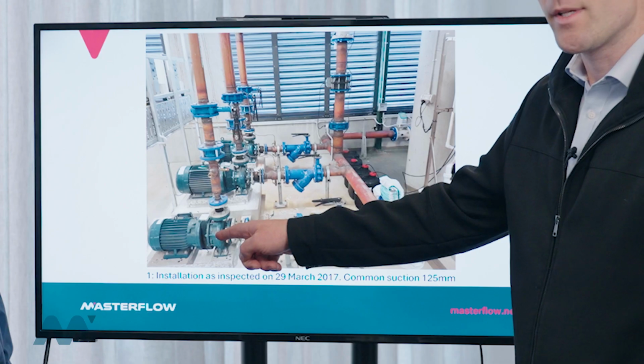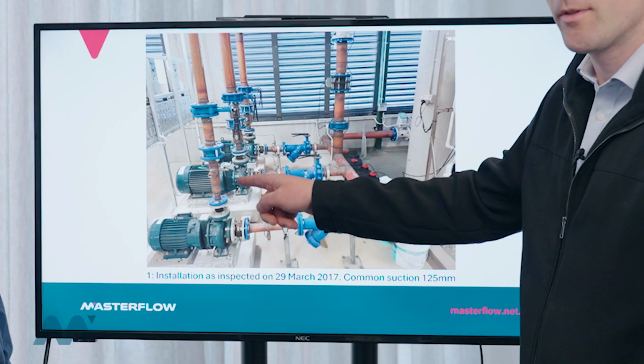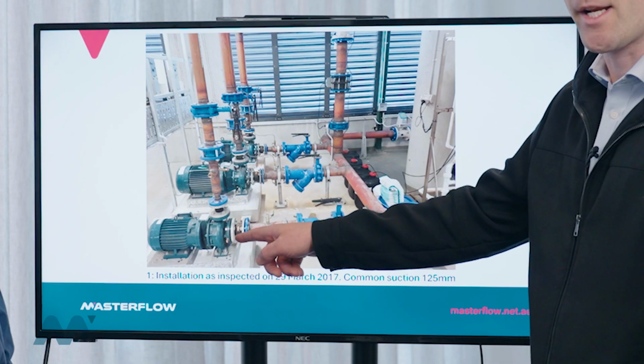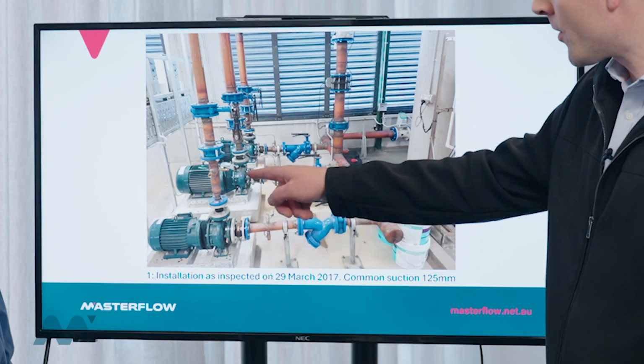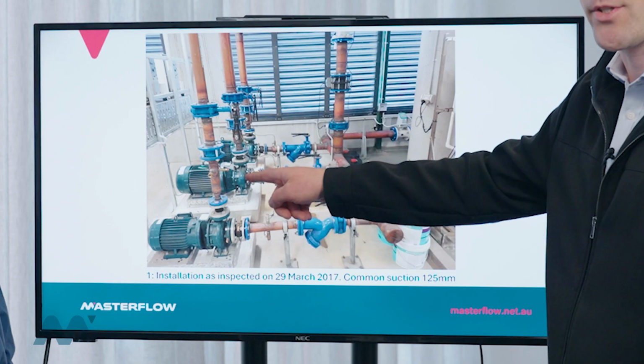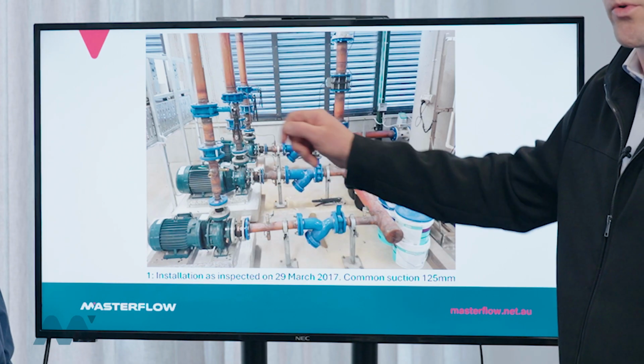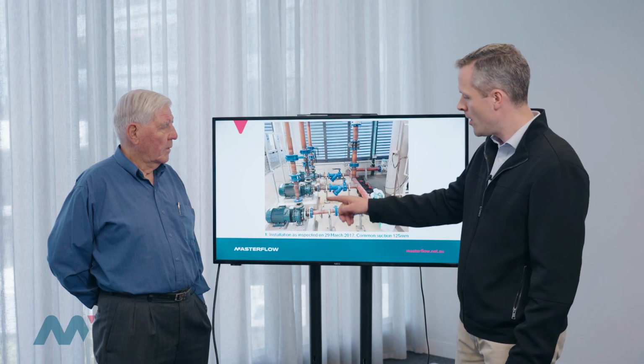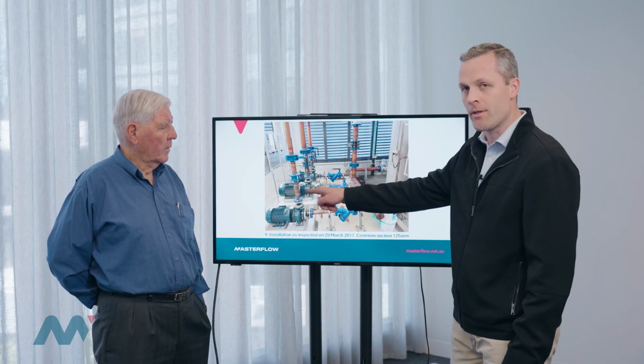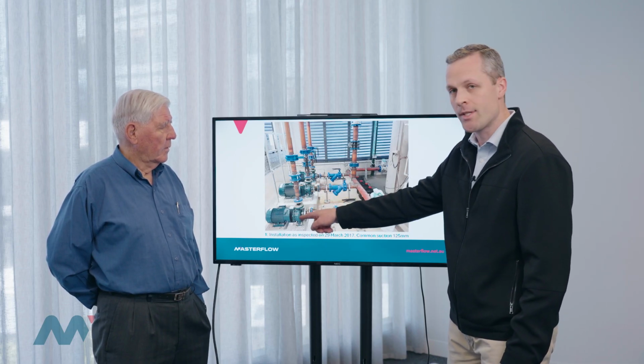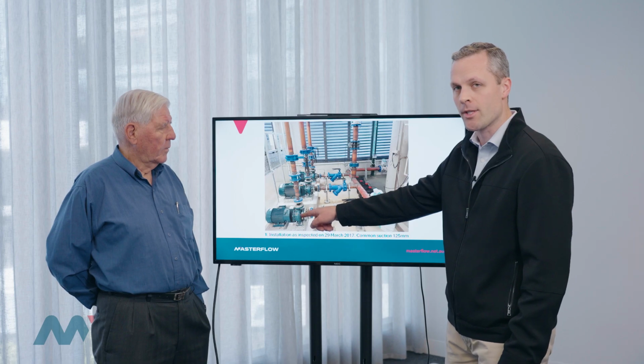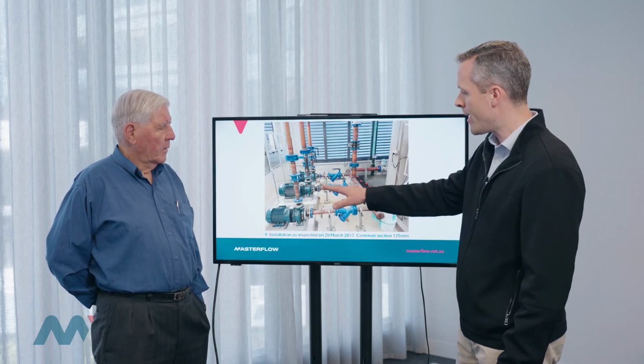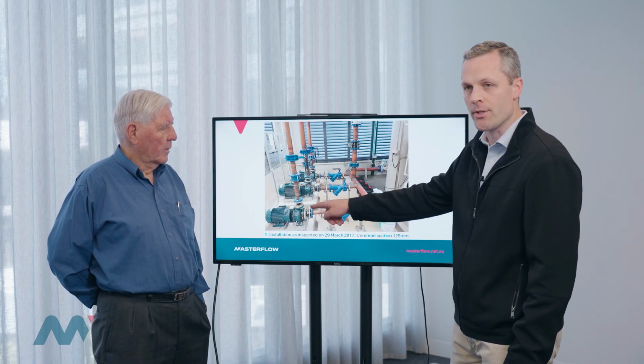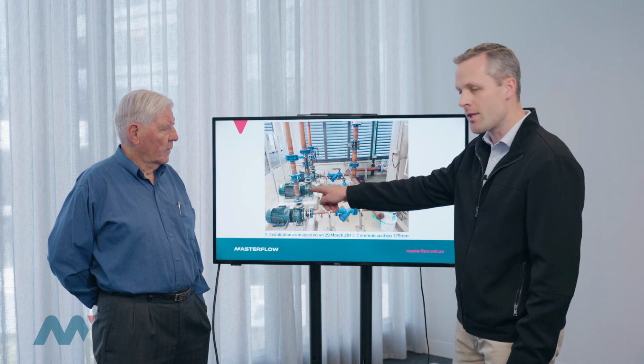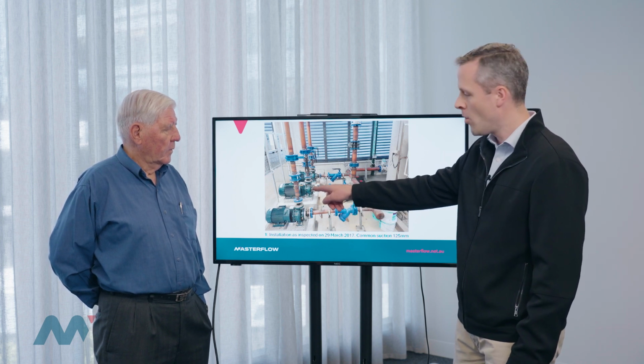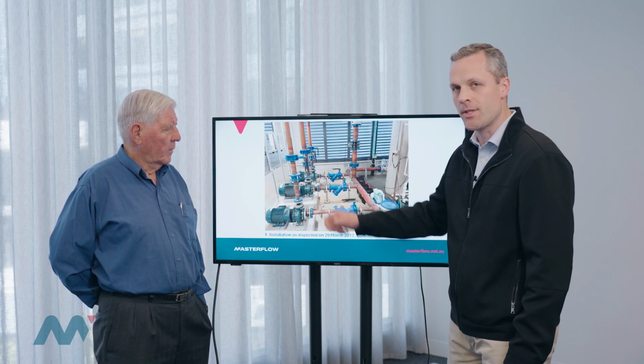This particular pump is a smaller size than these two because this pump is feeding the tenancy condenser water system, whilst these 2 pumps here, which are larger in size, are feeding the chilled water system. At any given time, we could have one of the pumps feeding the chiller system and the tenancy condenser water pump operating at the same time. What we don't have is all 3 operational at the same time. So it's either one of these 2 larger pumps operating or one of those plus the tenancy condenser water pump.